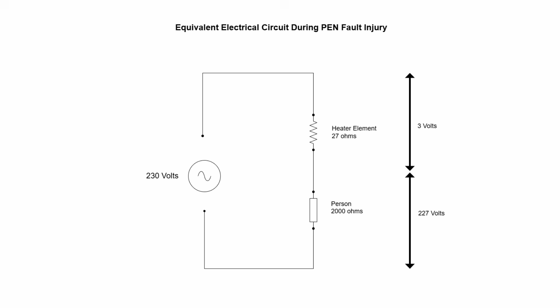No, it's only pen fault protectors that can help in this scenario, which, as it happens, they do by measuring for unusually high or low voltage differences between live and neutral. Low voltage being a trigger makes sense. In the simple fault condition we talked about, the neutral isn't connected to anything directly, so the voltage difference between live and neutral is nothing, and remains almost nothing during the fault, even when the person is attached.